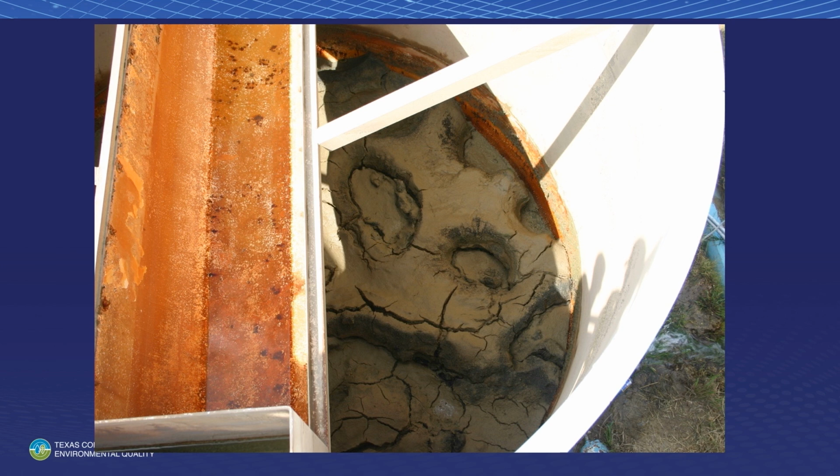And yes, those are holes in the filter, and that's crusted stuff on top of the filter. Noble got down in there and could hardly drive a stake through that stuff on top of that filter. And this hole right here went from this side of the filter all the way over to the other side. It was what, Noble, 4.5 foot across?